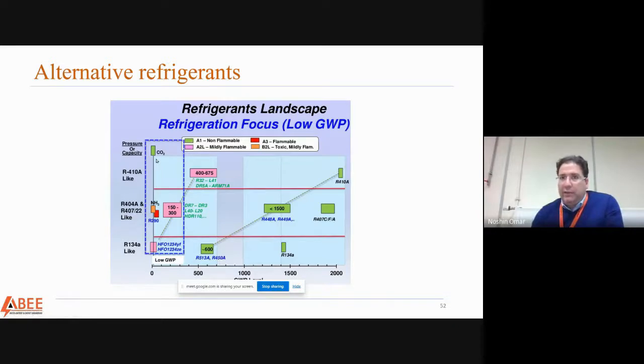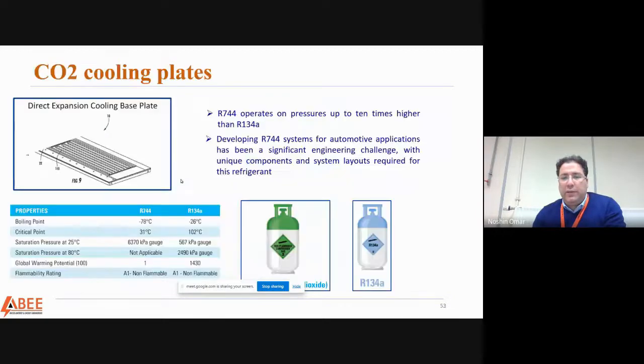That creates both an opportunity and a challenge. GWP should be lower because regulations are pushing toward more interesting refrigerant media. But to do even better, you have to accept pressures increasing from a few bars to 100 or 150 bars, which creates a lot of challenges and problems for the system, as we can see here.